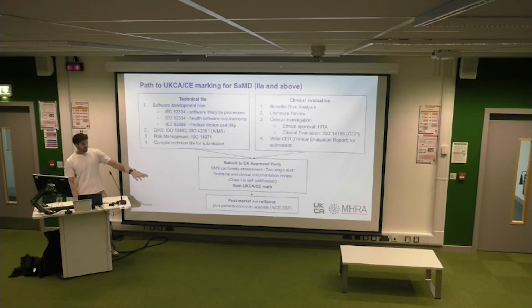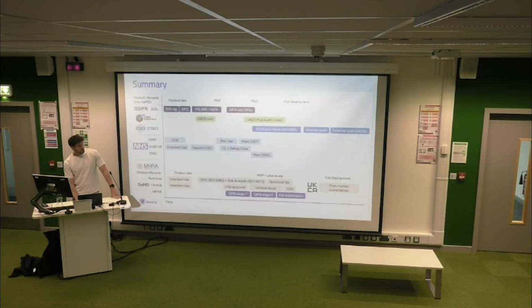And then there's also a requirement around economic analysis. You might have demonstrated your device is safe and clinically effective, but you also might have to demonstrate that it's cost effective. You can do this by doing a health economic analysis, and NICE have published what's called the Evidence Standard Framework, which is some guidance to do that body of work. And then some devices get NICE approval if they demonstrate this, which is useful for distribution across healthcare systems.